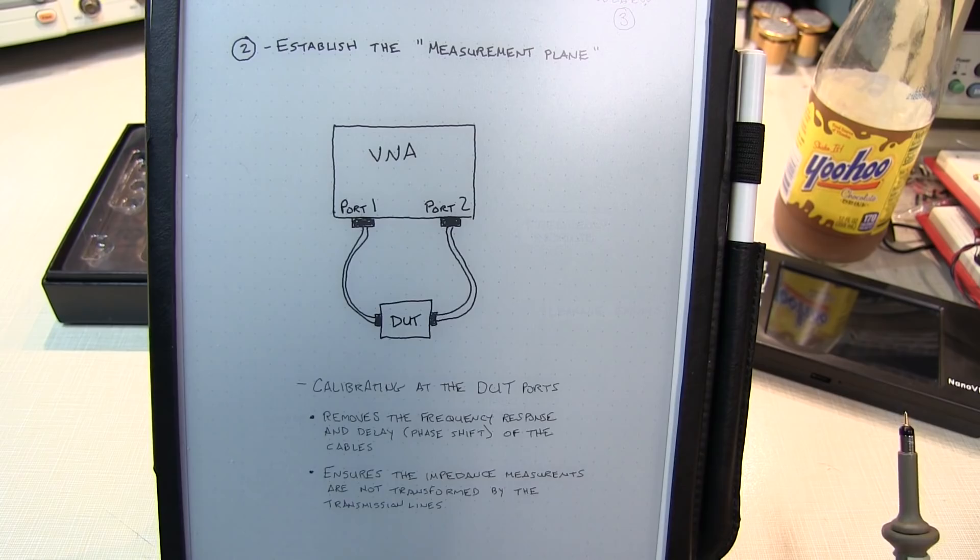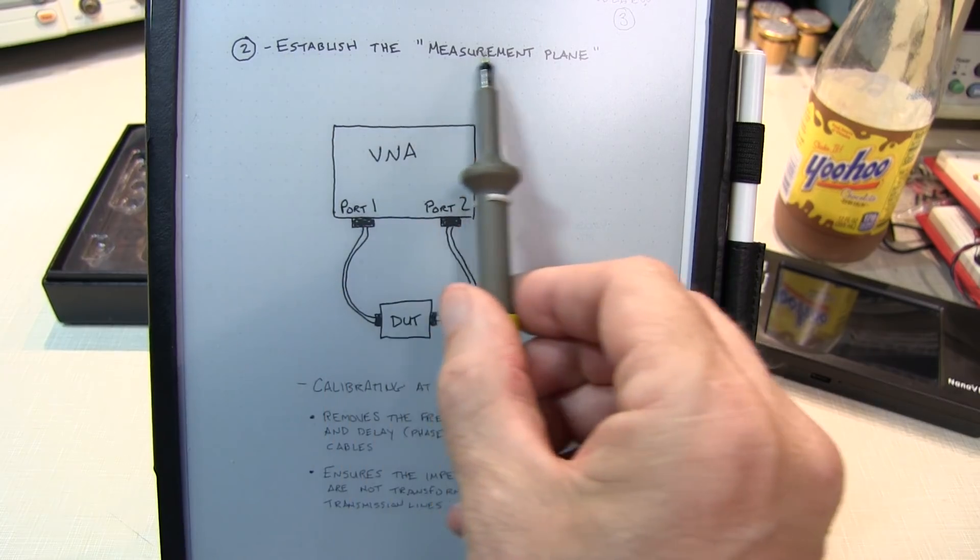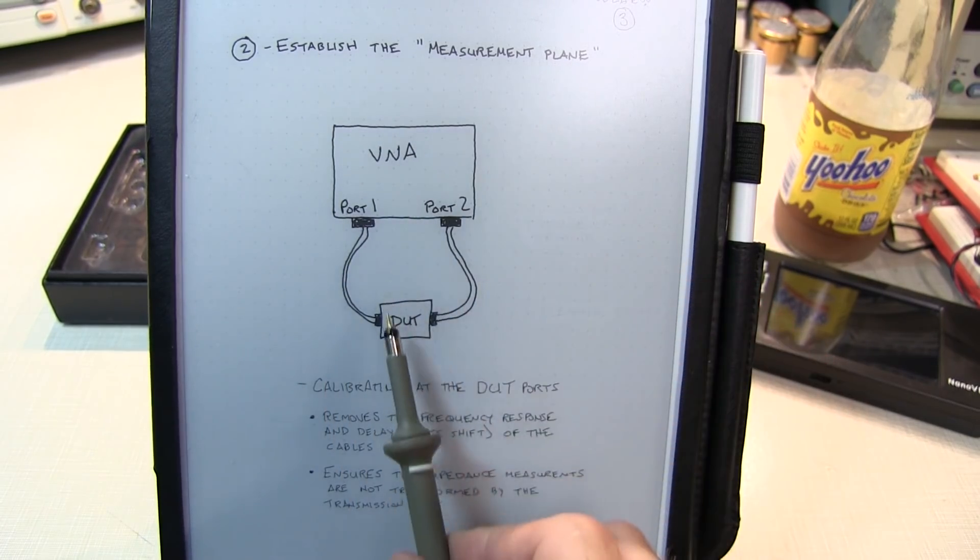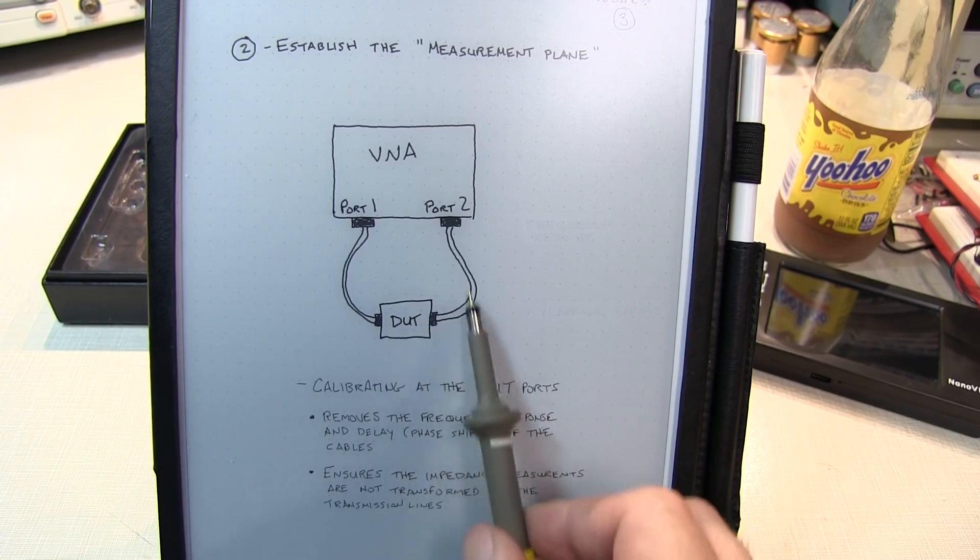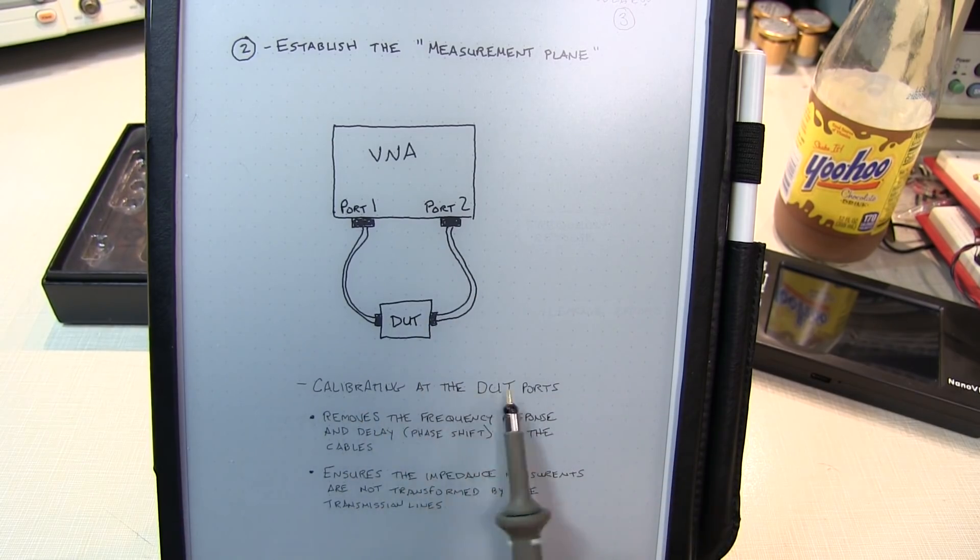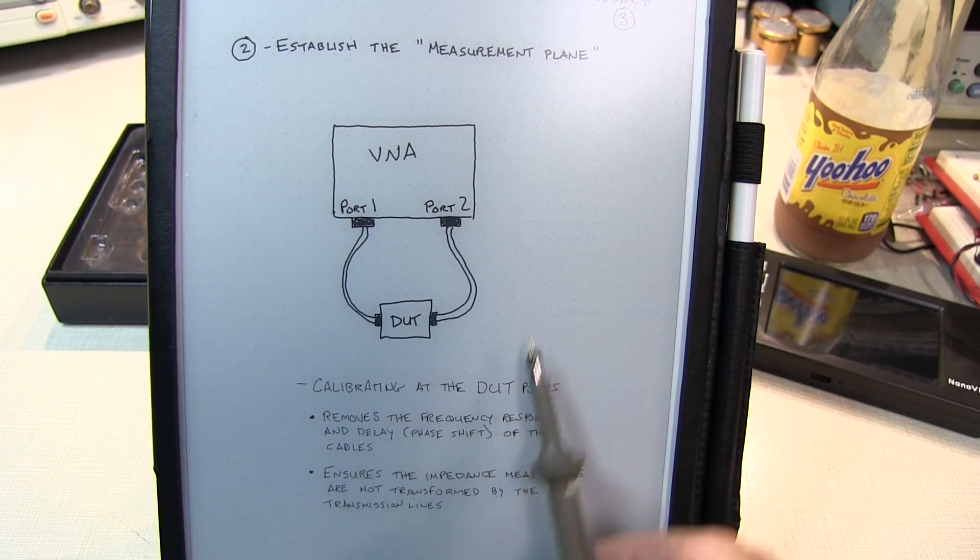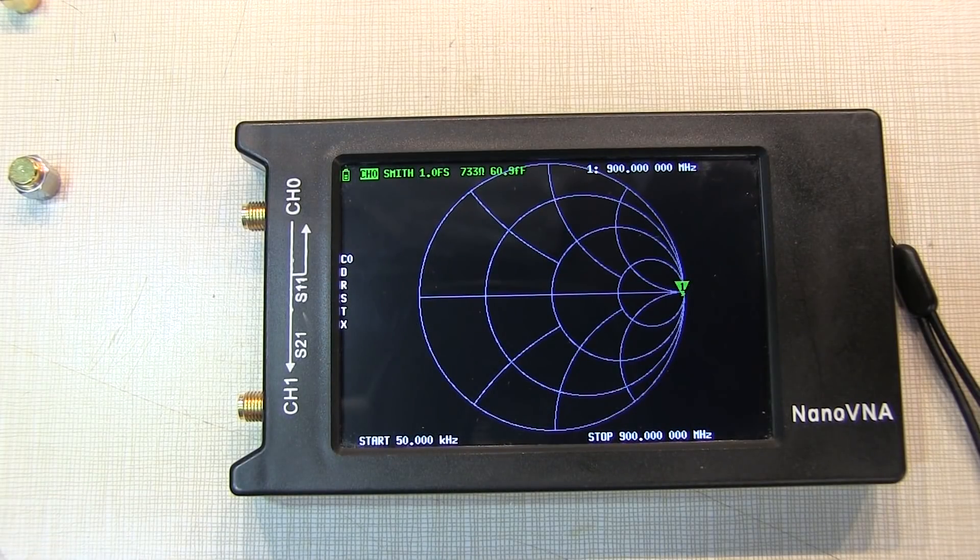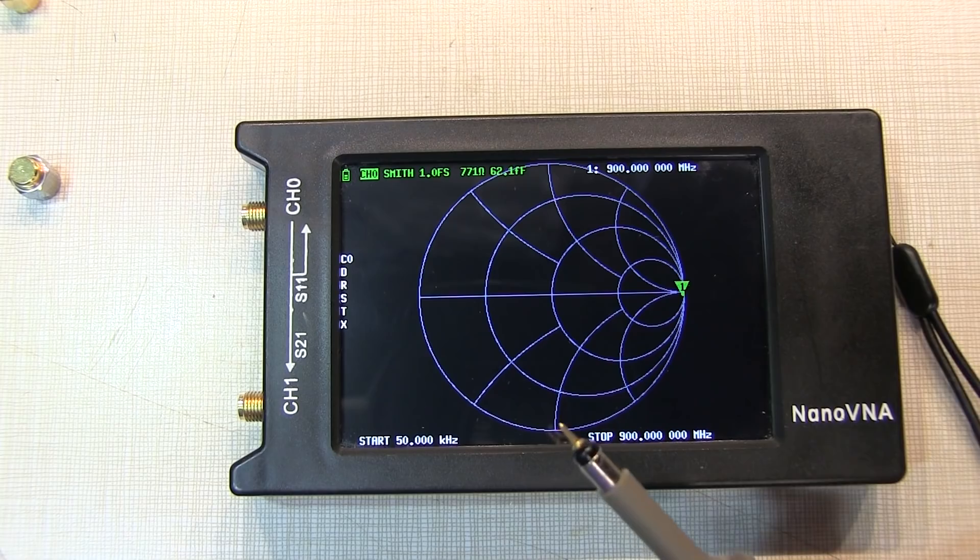Now the other important job of the user calibration is to establish the measurement plane or calibration plane, so that when we're measuring a DUT, we're measuring the terminal properties of the DUT and not being transformed by the interconnect to the DUT. So we do the calibration right at these DUT ports or as close as possible. And this removes the frequency response and delay or phase shift of the cables and ensures that the impedance measurements are not being transformed by those interconnect cables. Now the importance or the effect of that measurement plane can be shown very easily here with just using a Smith chart.